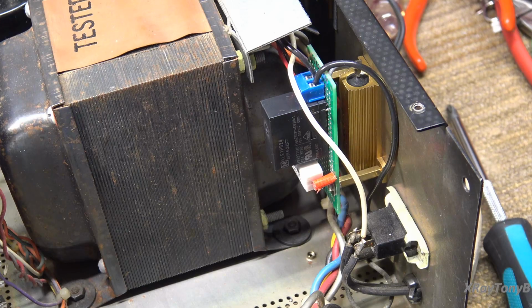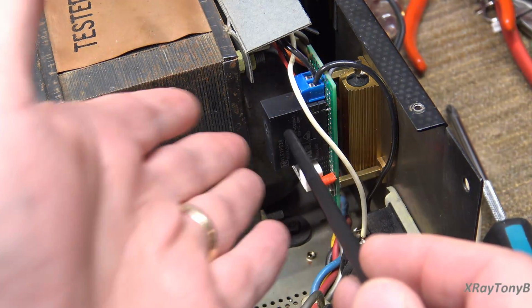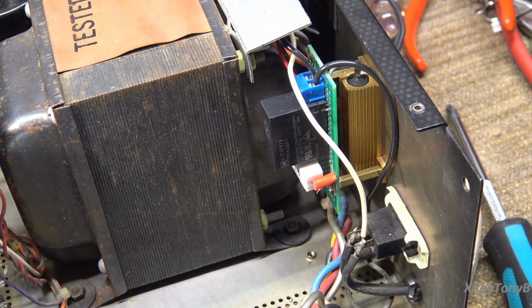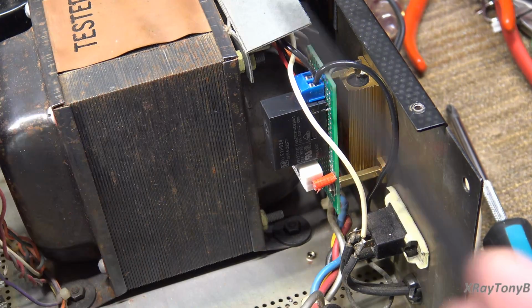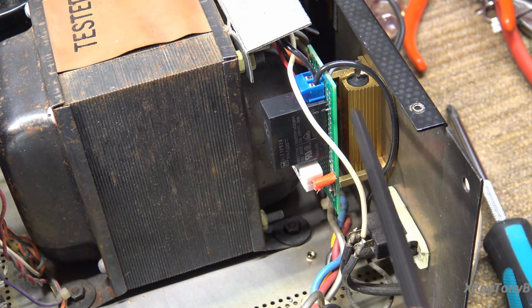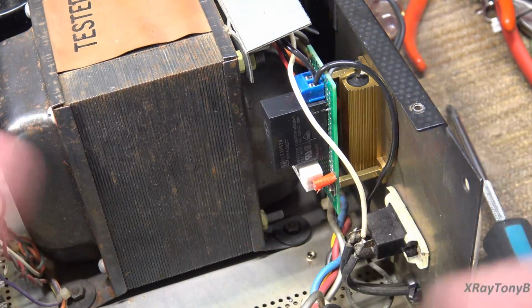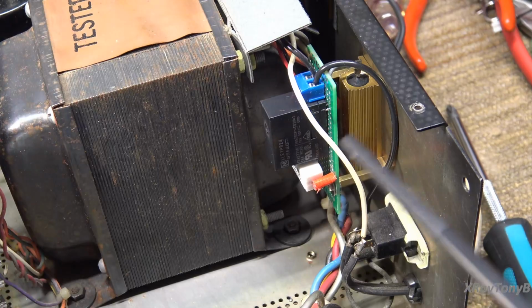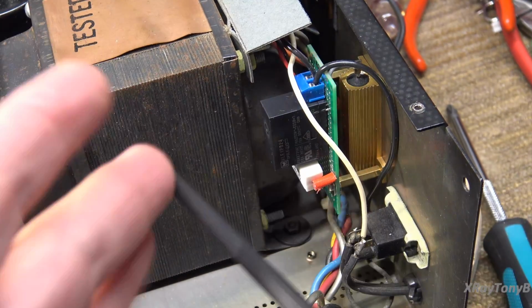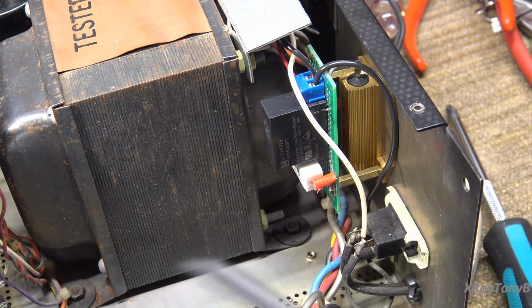So there is still a little bit of current limiting there, more so than if you had just a direct set of relay contacts. Another thing was, a lot of you got hung up on delaying the relay longer for limiting the current for a longer period of time before this comes in, or worrying about the contacts failing because of the arc.